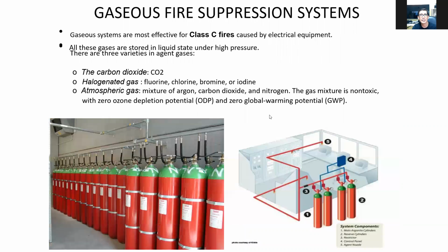Okay. Another one is the gaseous fire suppression system. This is for another type of fire, class C fire. This is connected to a manifold, and this manifold will distribute carbon dioxide, or halogenated gas, which is fluorine, chlorine, bromine, or iodine, or atmospheric gas inside a building. So this is commonly used in call centers. This is what they use in data rooms, or CCTV rooms, or in places where there is electronics. Okay.